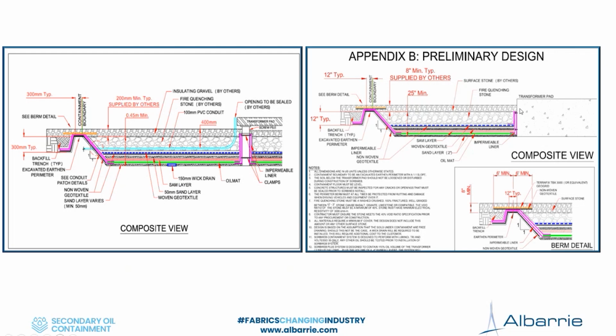If the pad is shallow, obviously we have a berm here to prevent undermining of that pad when they're doing the excavation. So that can have some impact on the footprint overall. But again, there are trade-offs in all of these things you have to look at. The berms, as I mentioned, are usually protected by that geogrid, which allows you full access for equipment drivability. So it's designed to withstand a maintenance truck, or about 24,000 kilograms per tridem axle. Some of our containment systems with some of our clients are designed for highway traffic as well. So we just need to know that information and we can design the containment accordingly.